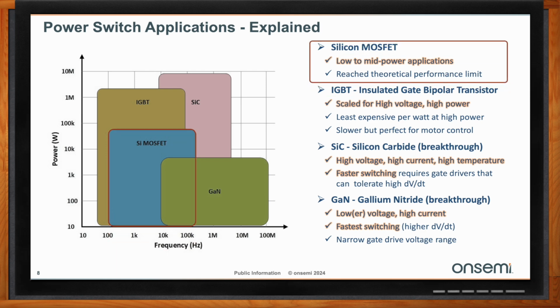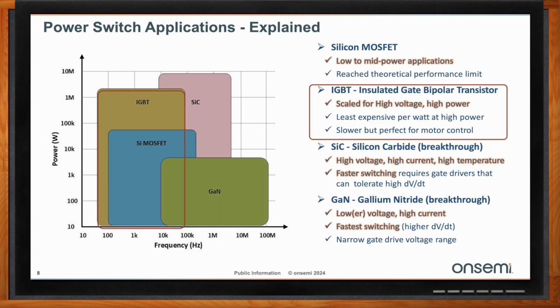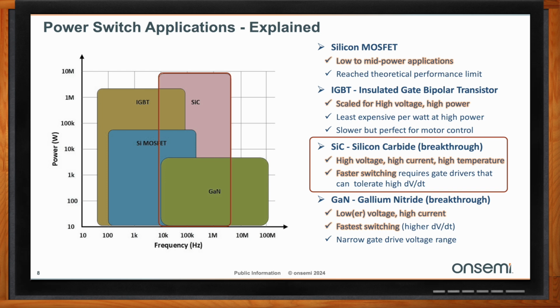The silicon MOSFET is really for low to mid power applications for these motors. They've pretty much reached their theoretical performance limit. The IGBTs, as you can see, they can go up to beyond a megawatt. They're scaled for high voltage and high power. It's an excellent bang for your buck for high wattage versus cost. But then you can see the silicon carbide actually switches faster beyond a megahertz and also up to 10 megawatts. It's a real breakthrough in technology.